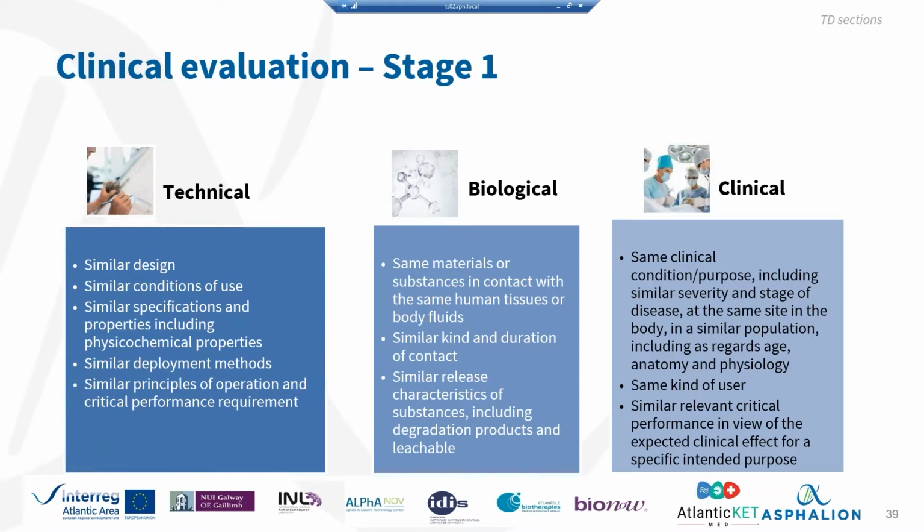Okay, so what does that mean? From a technical point of view, it means that it has to have a similar design, similar conditions of use, similar specification, similar deployment methods, and similar principles of operation. Okay, it's got to be technically equivalent. From a biological perspective, it means that the materials and substances have to be the same. It has to have the same kind and duration of contact with the patient. It has to have similar release characteristics of substances, including degradation products and leachables.